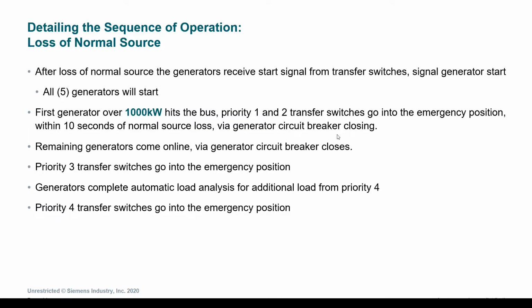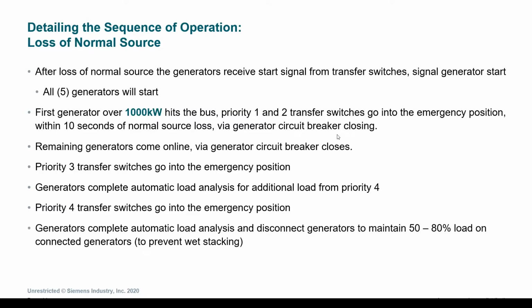As soon as that load capacity from the generators is confirmed, the priority 4 transfer switches will go into that emergency position. At this time, the generators will complete that load analysis again, and now, however, it will disconnect any generators so the remaining generators are at a 50 to 80% load for all the generators that are connected. And this is to prevent wet stacking and damage to those generators, as well as for ideal fuel consumption in operation.